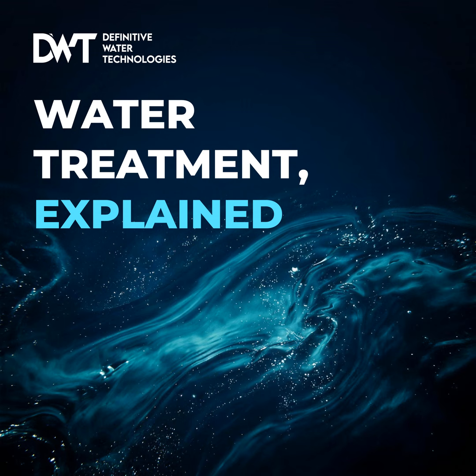Okay, the chemicals survived the pump, the elastomers are holding up, but we still have to get it into the process water. The last inch. Yes. The sources say this is where the most dangerous commissioning faults occur, the unvalved siphoning nightmare. We have to remember, a metering pump only meters. It displaces liquid. It does not regulate flow. Okay. If the path from your day tank to your line creates a pressure gradient where the liquid wants to flow on its own, it absolutely will.